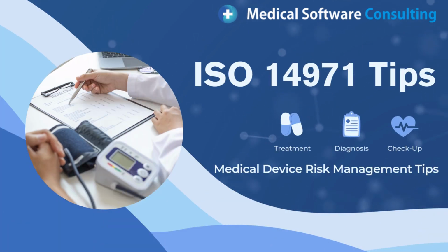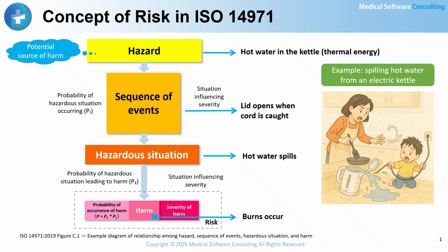Medical Device Risk Management Tips. Today, I will explain the concept of risk in ISO 14971 using the example of spilling hot water from an electric kettle. This diagram shows the flow from the top, starting with the hazard, which is the potential source of harm. Then a sequence of events occurs, leading to a hazardous situation, and finally resulting in harm.